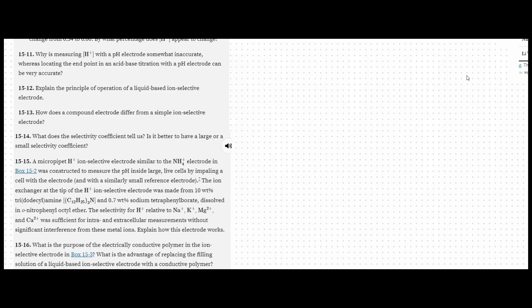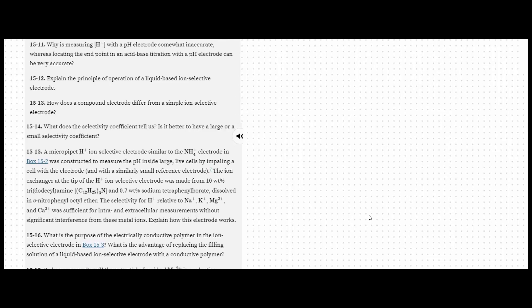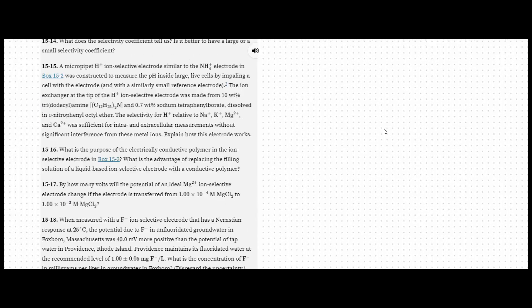Alternatively, the second membrane may contain a substance like an enzyme that reacts with the analyte to generate some species that the ion-selective membrane would react to.